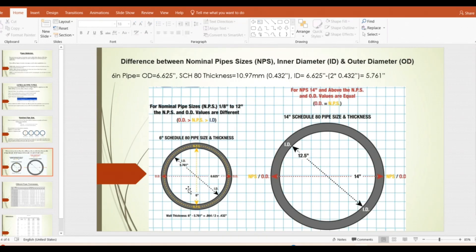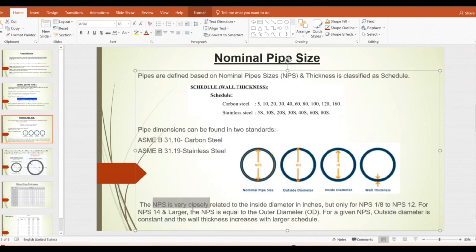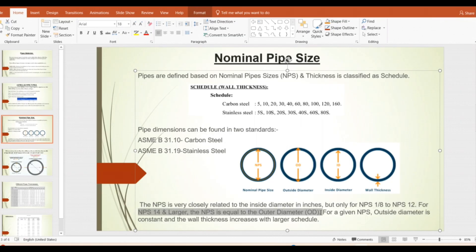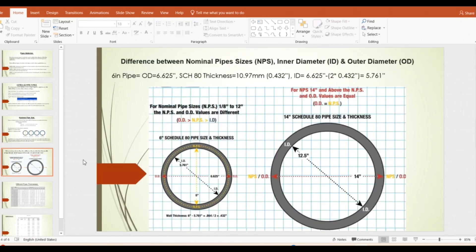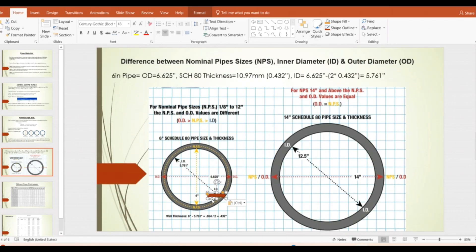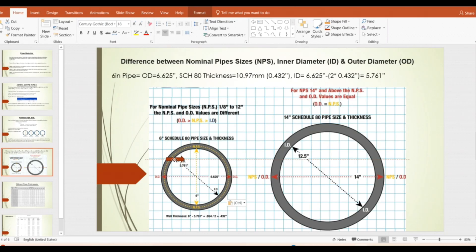An important concept: the nominal pipe size is very close to the inner diameter, but only for pipe sizes from 1/8 inch up to 12 inch. For 14 inch and larger, the Nominal Pipe Size equals the outer diameter. So for 14 inch and above, outer diameter equals NPS and only the inner diameter changes. For less than 12 inch, outer diameter, inner diameter, and nominal pipe size are all different values.